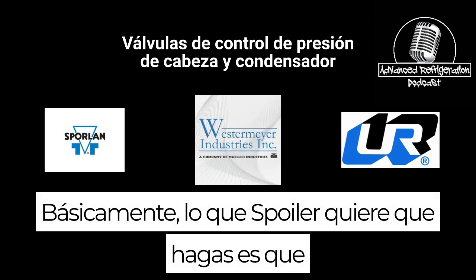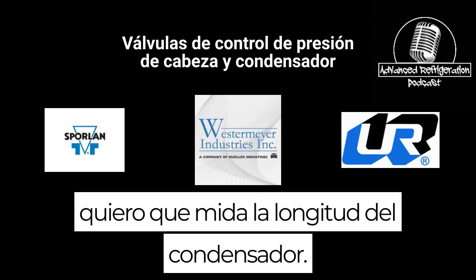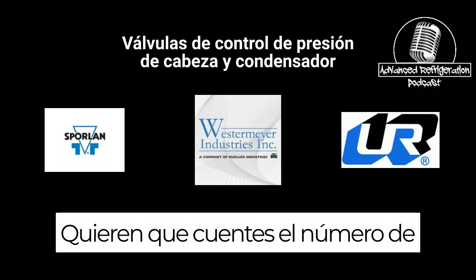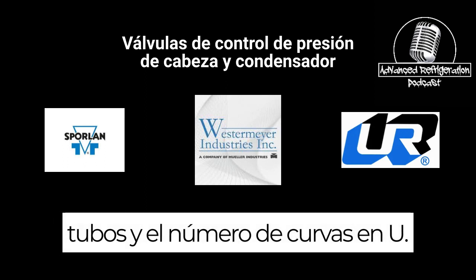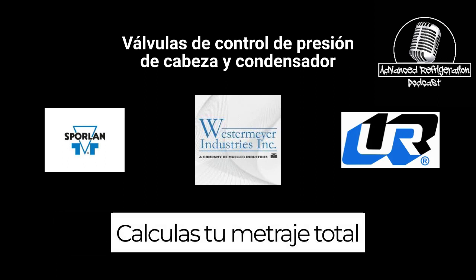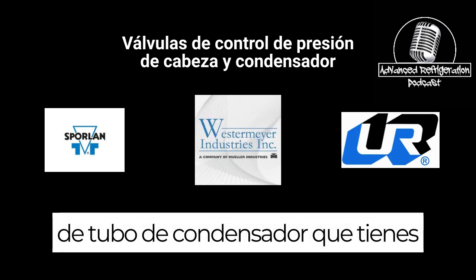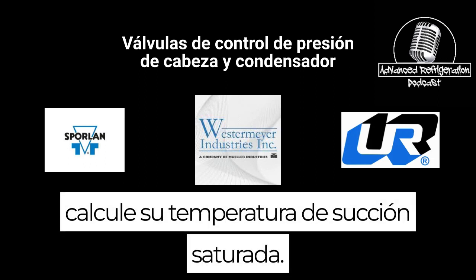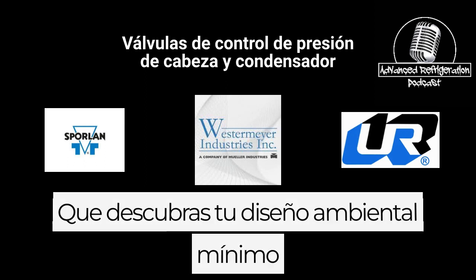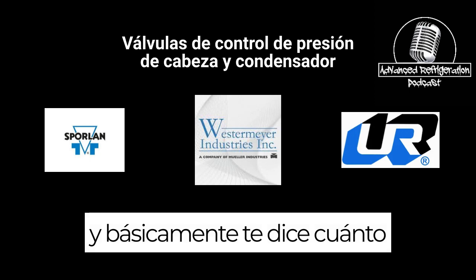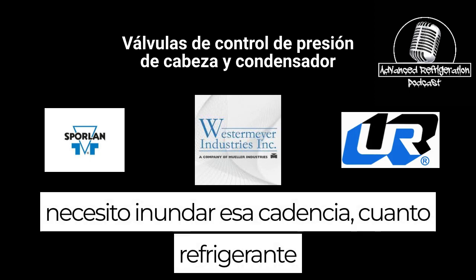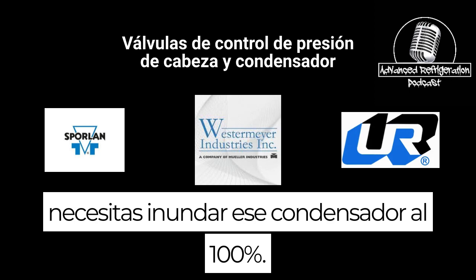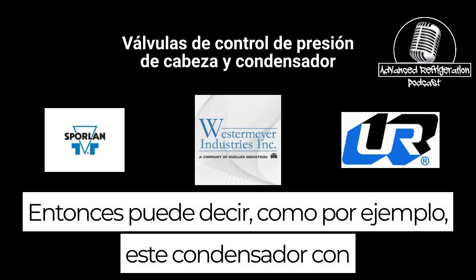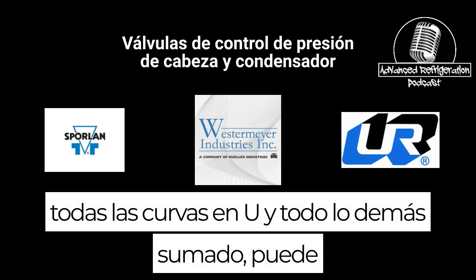Basically, what Sporlan wants you to do is measure the length of the condenser. They want you to count the number of tubes and the number of U-bends. You figure out your total footage of condenser tubing. You figure out your saturated suction temperature. Then you figure out your minimum ambient design. And it basically tells you how much refrigerant you need to flood that condenser 100%. So it may say, for example, this condenser, with all the U-bends and everything else added up, may have 1,000 feet.